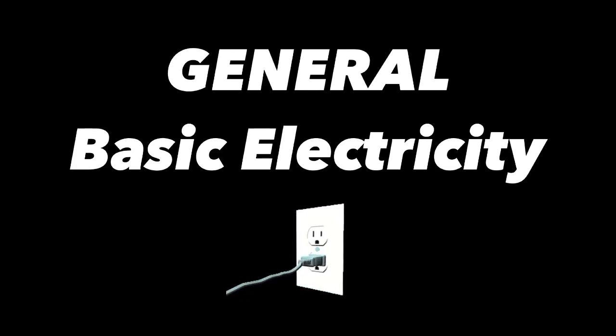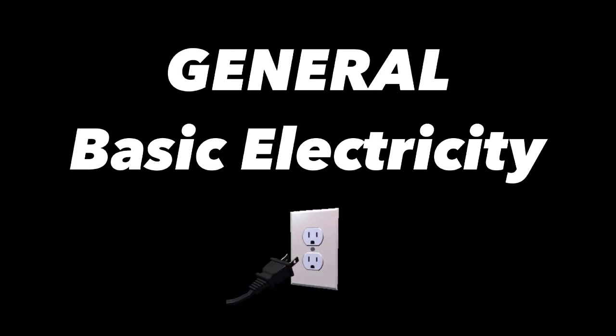How is it possible to know when a nickel cadmium battery is fully charged? Completely discharge the battery and give it a constant current charge of 140% of its ampere hour capacity.